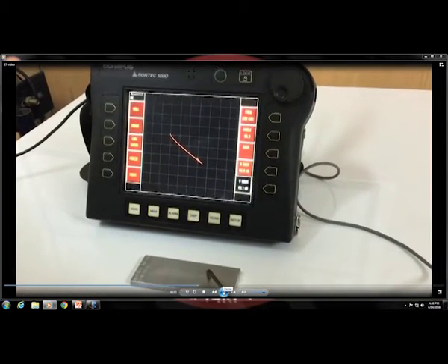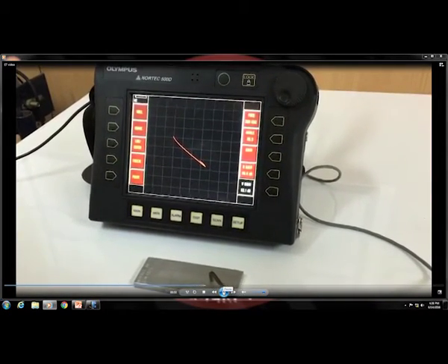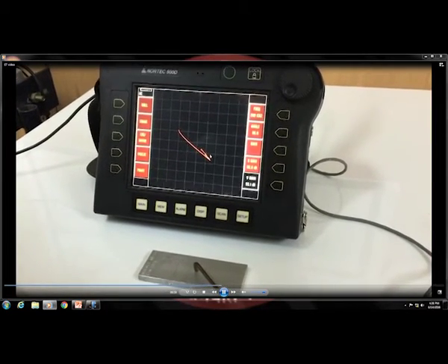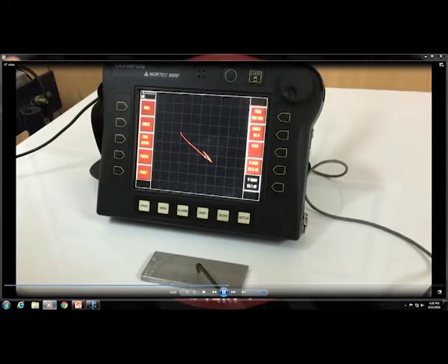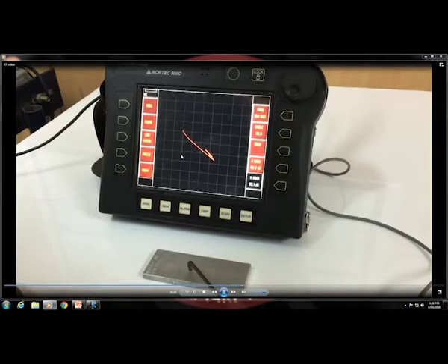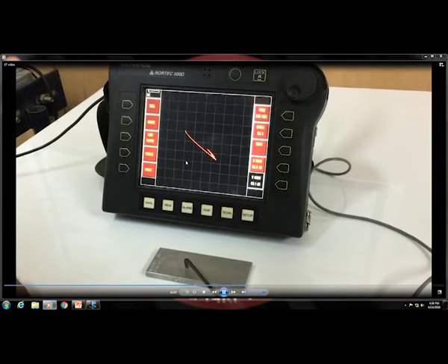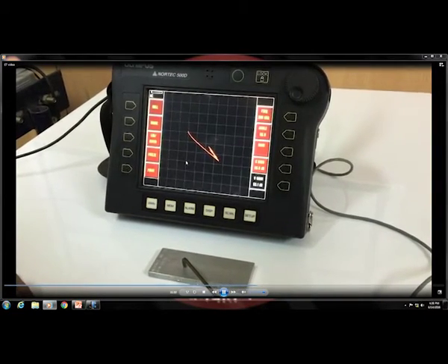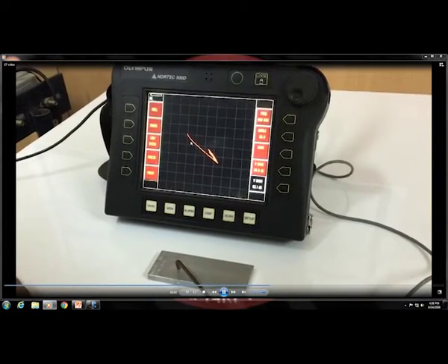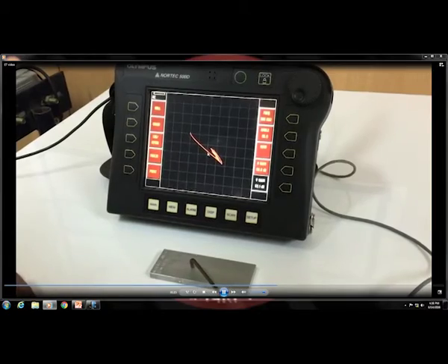Okay, and once I move it over the first crack, which is the smallest one, you can see a small signal coming. Then at the second crack you can see a bigger crack signal coming, because that is a bigger defect. And then I am going to the third one now, and you can see a further bigger crack signal coming out over the lift off curve.